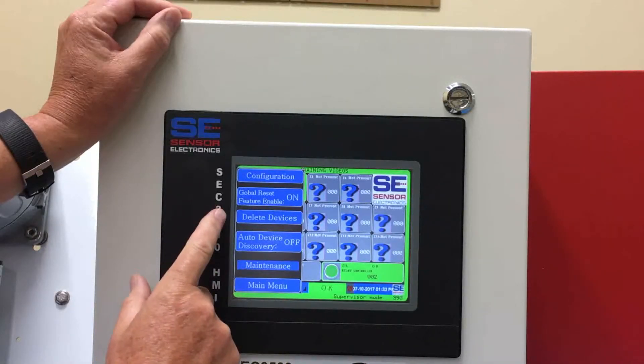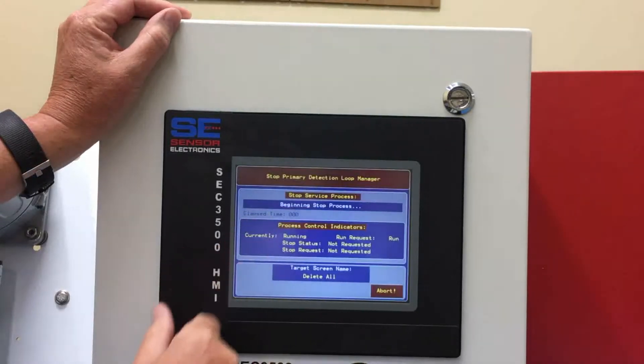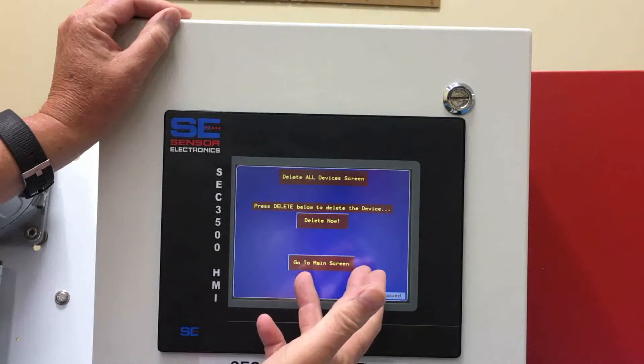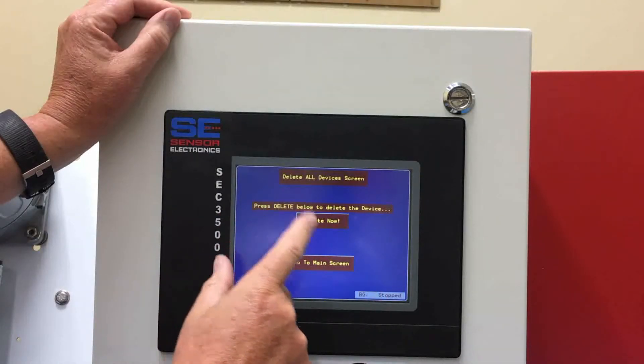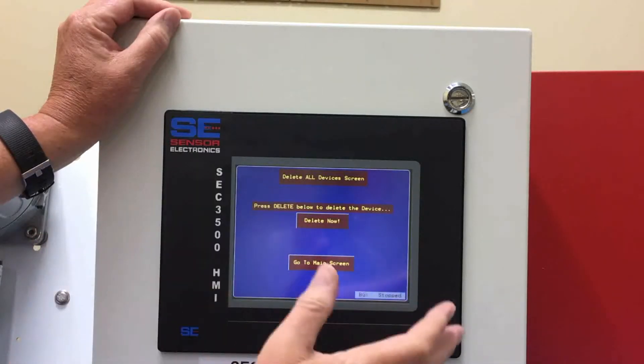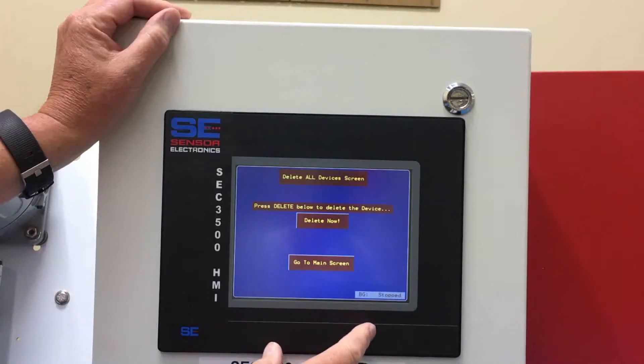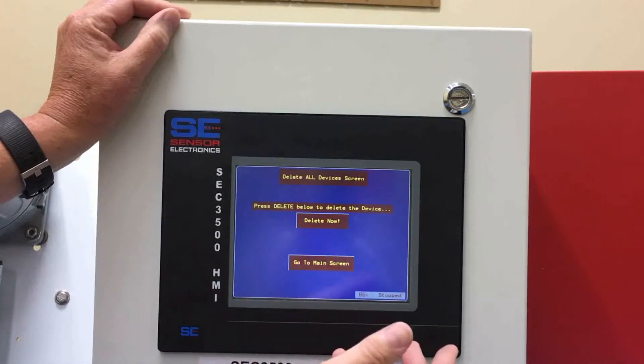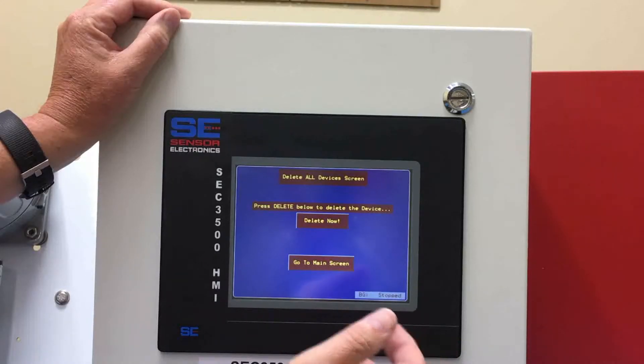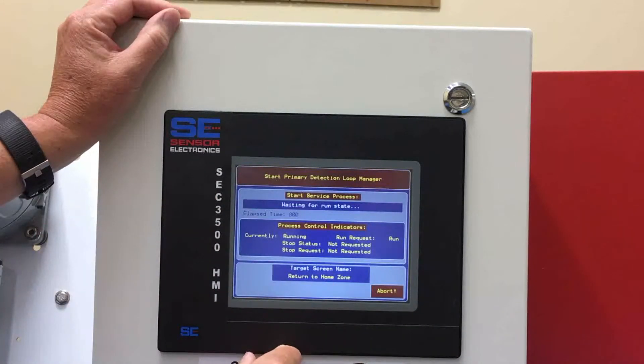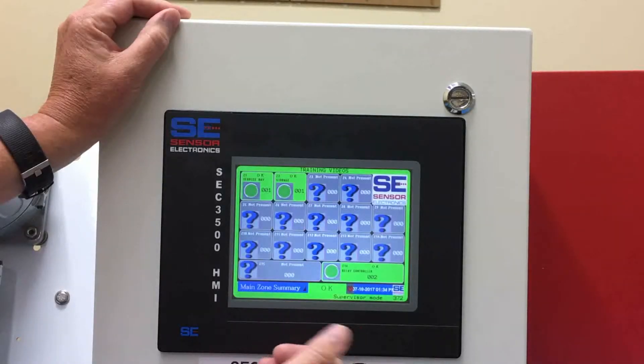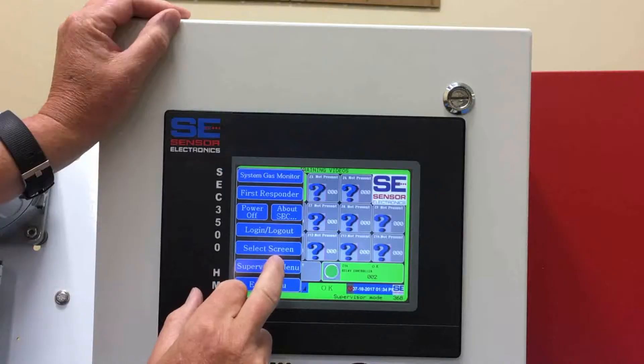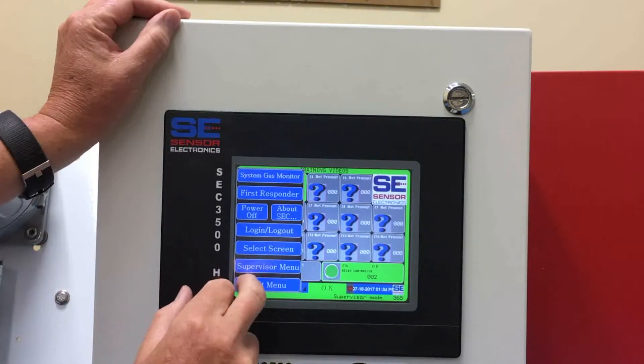We also have the capability of deleting devices from here. If you press delete now, it's going to delete every detector, every relay module, and every sensor on the system. Then you'll have to reprogram all the relays — the IDs and everything will stay the same, but you'll have to reprogram the relay module. This is really a last resort if you have problems with the system.